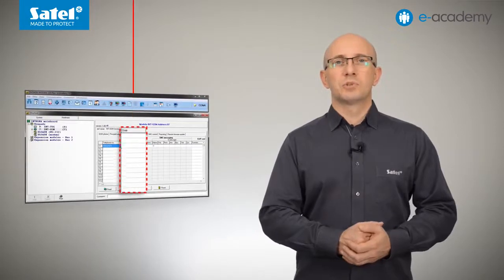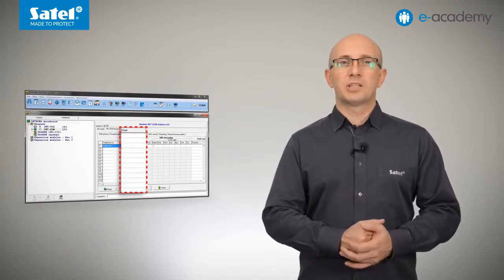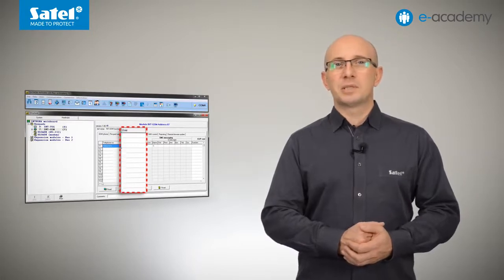The same telephone numbers can be used to control the Integra system by means of SMS messages and the clip service. Important note, in order to be able to control the system via SMS messages or clip service using a given telephone number, the number should be associated with the user registered in the control panel.